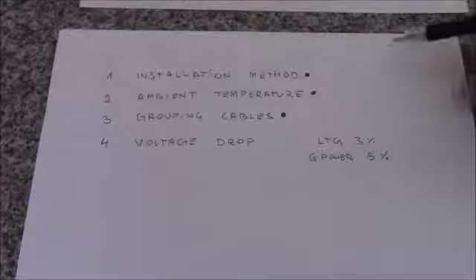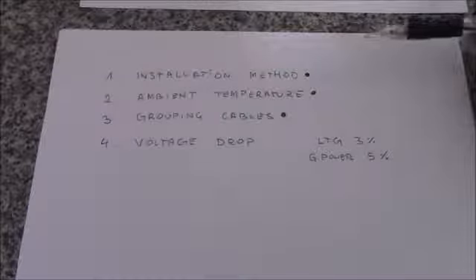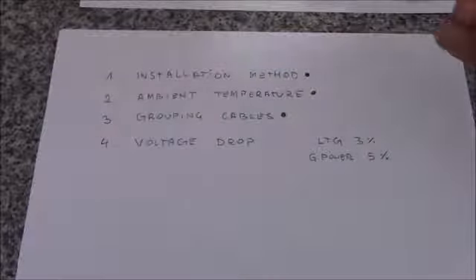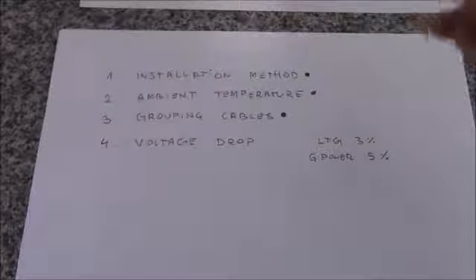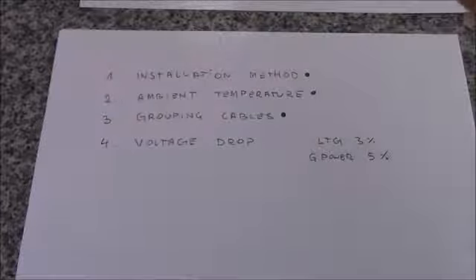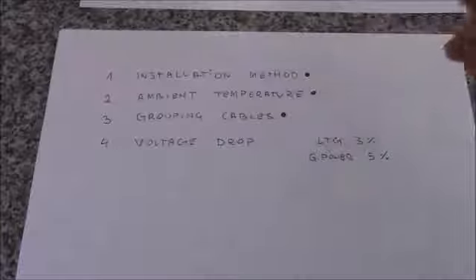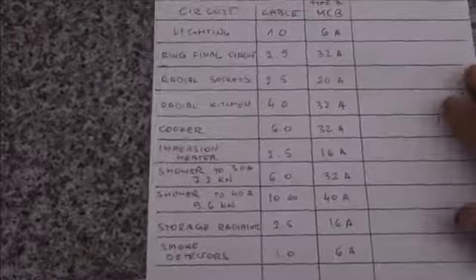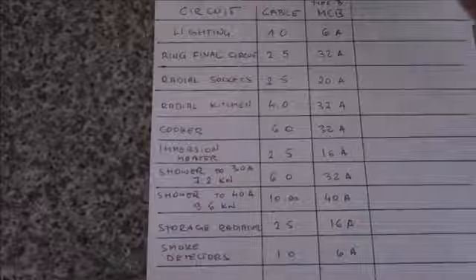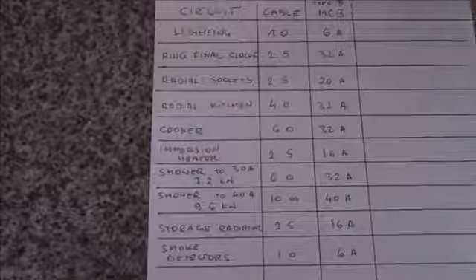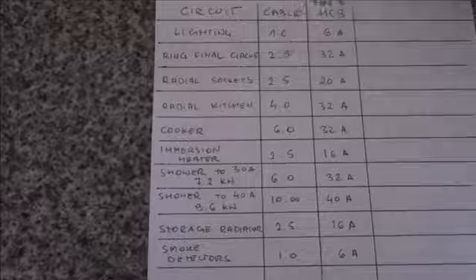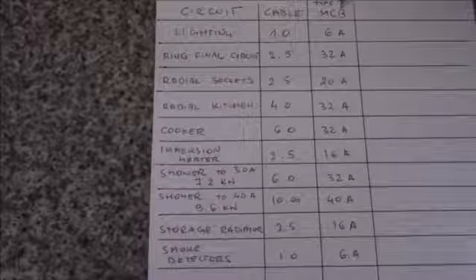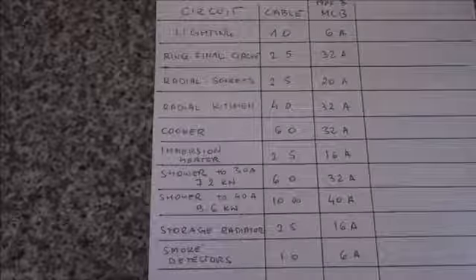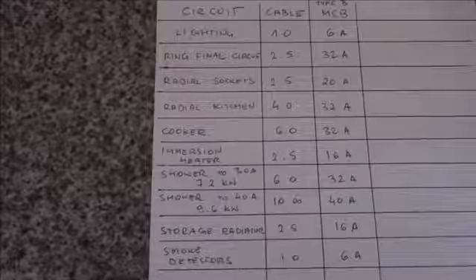So there are a lot of things to consider when choosing the right cable for the circuit, but to make life easier, I'm going to give you a list of the most commonly used cable sizes and circuit breakers for each circuit in a house. So that's the list I was talking about, and I'll leave it for a few minutes. Here we've got the circuits, the cable size, and the miniature circuit breaker type B, which is the most commonly used in the UK.